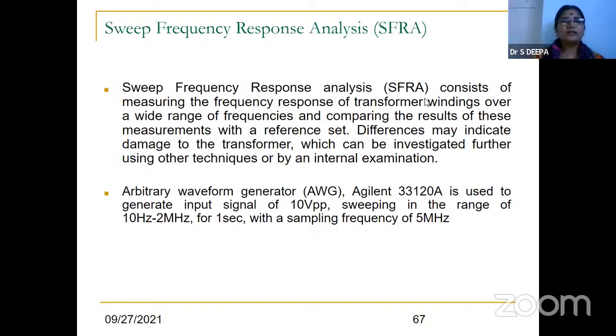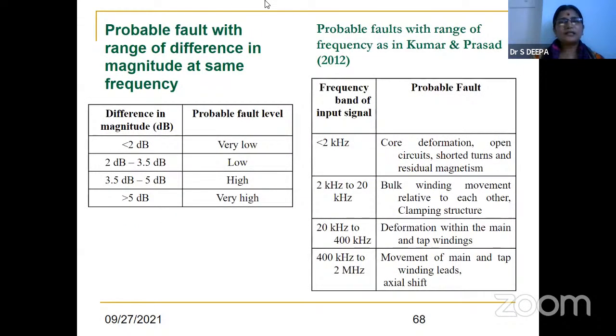Now the sweep frequency response consists of measuring the frequency response of the transformer winding over a wide range of frequencies and comparing the results of these measurements with a reference set. Differences may indicate damage to the transformer, which can be investigated further using other techniques, such as internal examination. So in the literature, we also have to say from where we have taken the data.